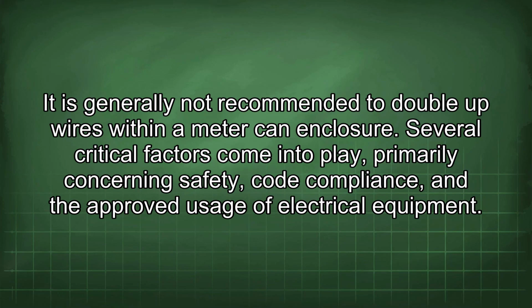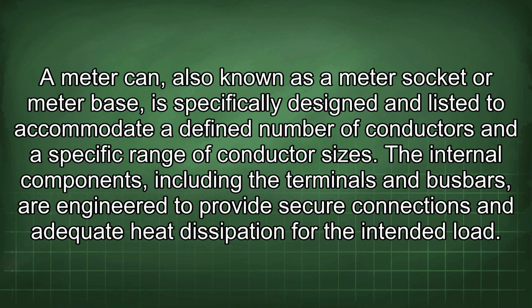It is generally not recommended to double up wires within a meter can enclosure. Several critical factors come into play, primarily concerning safety, code compliance, and the approved usage of electrical equipment. A meter can, also known as a meter socket or meter base, is specifically designed and listed to accommodate a defined number of conductors and a specific range of conductor sizes.